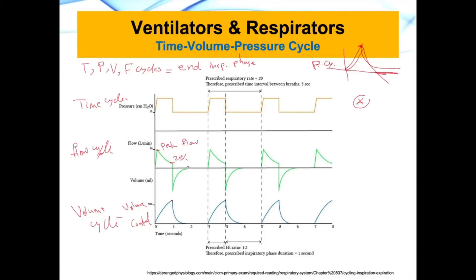In the flow cycle, we are increasing the flow, and then at a certain point the flow will start getting lower and lower — smaller and smaller because of resistance in the lungs. We are setting 25% of the peak flow as the ending point: open the valves for exhalation and stop pushing gas inside the lung. That is what we mean by a flow cycle. Keep in mind that cycles mean the thing that is going to stop the pushing of air inside the lungs. Pressure control and volume control are two different things from pressure cycle. Time cycle is a pressure control; a volume cycle is a volume control because once the volume reaches a certain point, we stop pushing air inside the lungs.